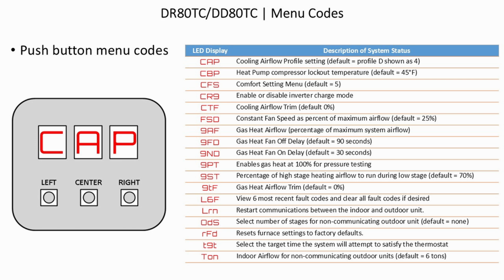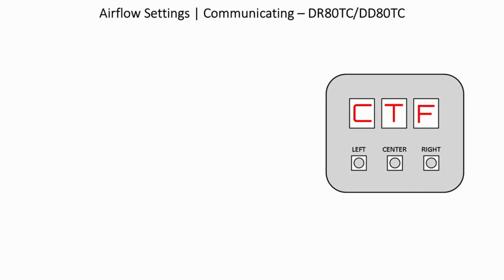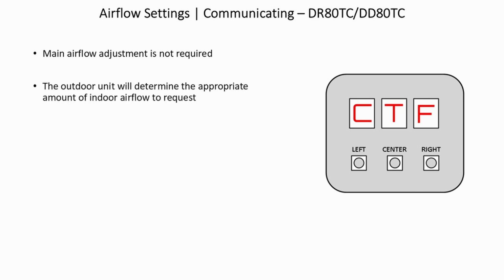The DR80TC and DD80TC examples are shown. The full list is found in the installation manual. Airflow settings for communicating DR and DD 80TCs. The main airflow adjustment is not required. The outdoor unit will determine the appropriate amount of indoor airflow to request.